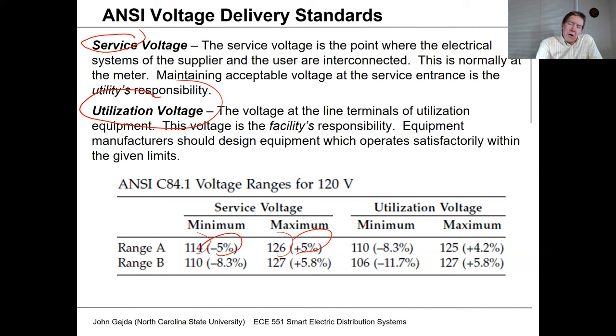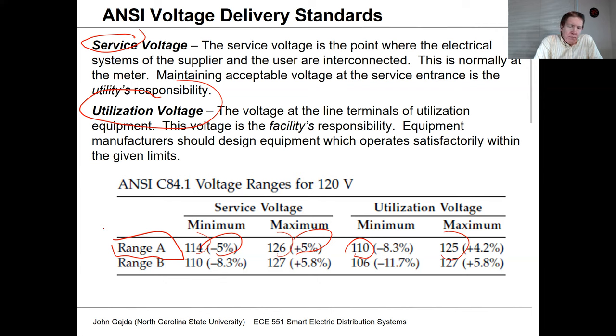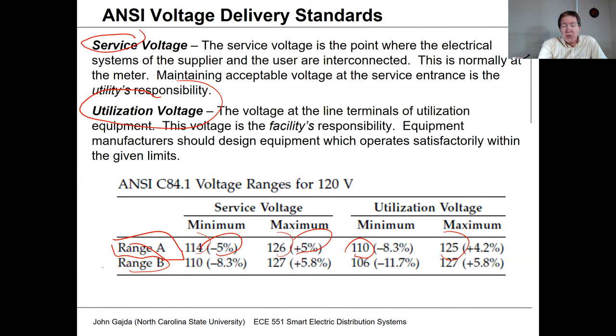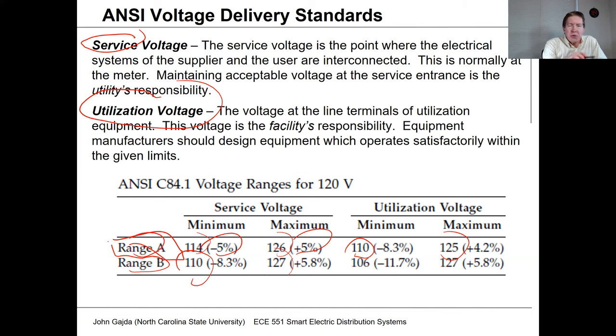ANSI standards allow for utilization voltage to get as low as 110 or as high as 125 for Range A service under normal conditions. Range B corresponds to emergency conditions — like a major storm or generation/transmission issues — where service voltage can vary within a wider range, between 110 and 127 on a 120V basis. Normally utilities try to adhere to Range A.